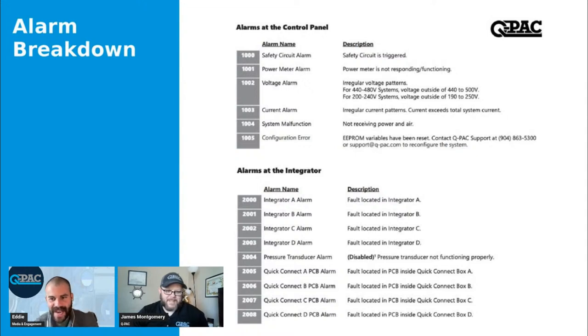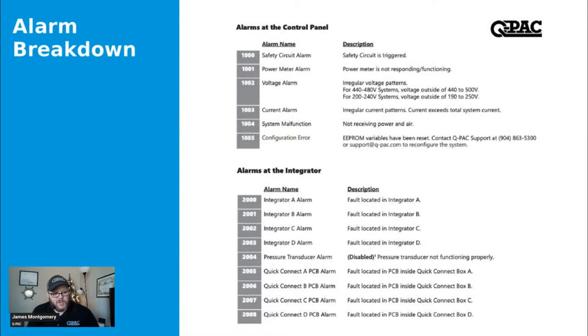So Douglas was asking if alarms 2000 to 2003 are shutdown alarms. No, that's a good question. I was hammering that home. In fact, the only shutdown alarm in this whole list is the very top one, and that's the safety circuit. Those are not shutdowns. But what it is telling us, 2000 through 2008, minus the 2004 pressure transducer, is that I may have an issue communicating with one or more of your fans.